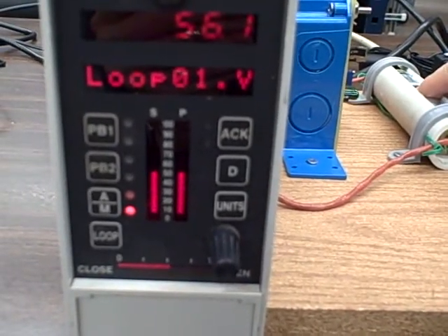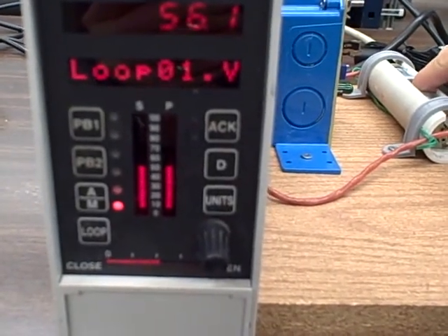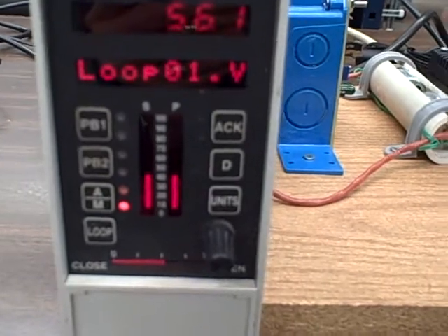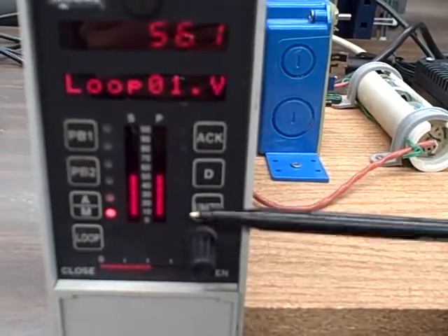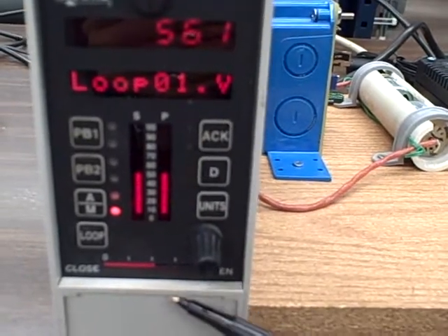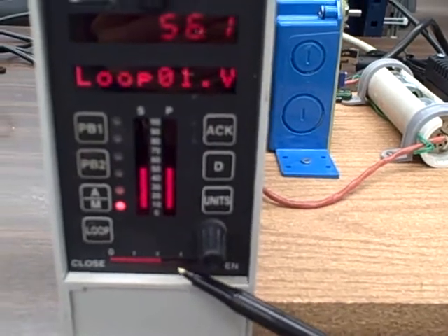Now I let go, and I touch the shaft, and now I let go, and I touch the shaft again. So you can see the effect of my finger physically loading down the motor, making the bar graph go up and down on process variable. No response is seen at the output because the controller again is in manual mode and is taking no corrective action.